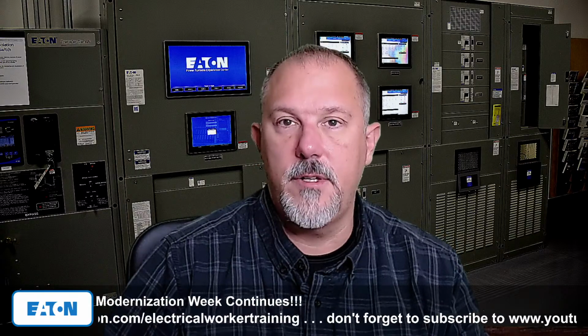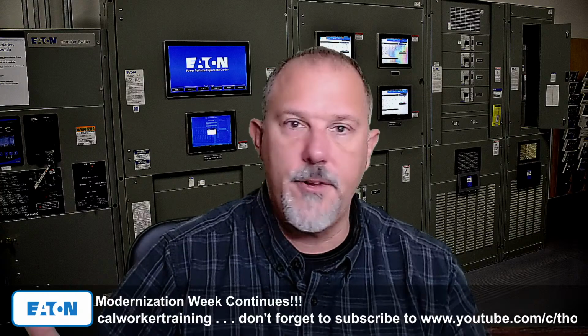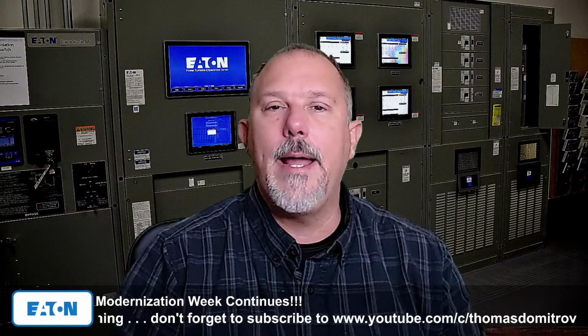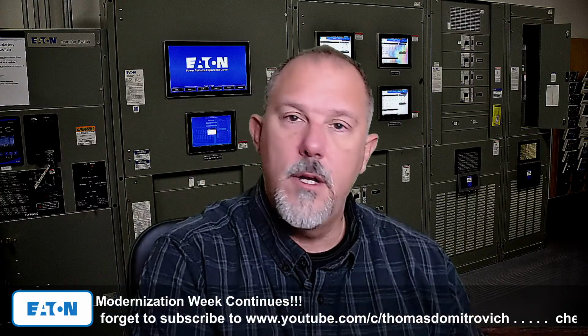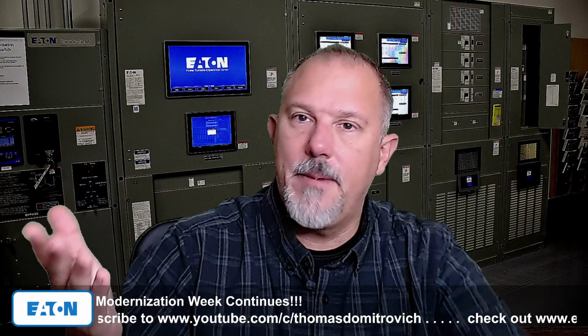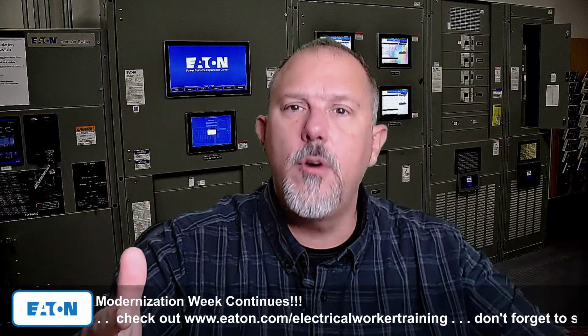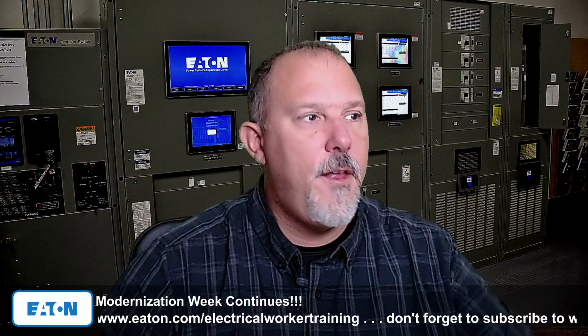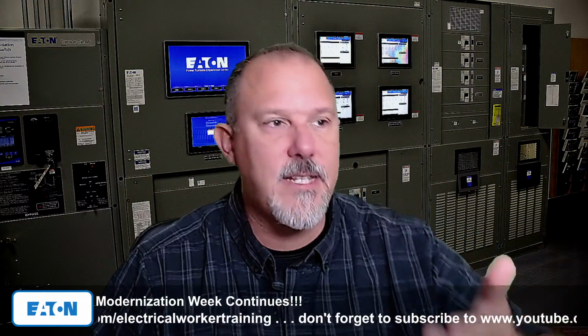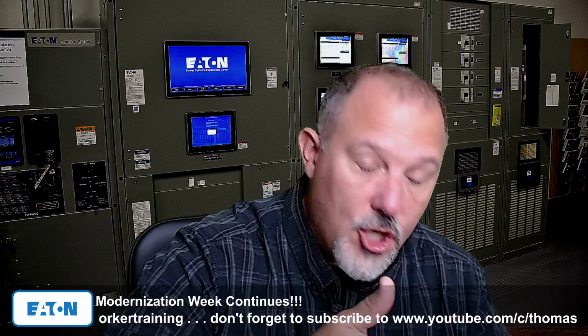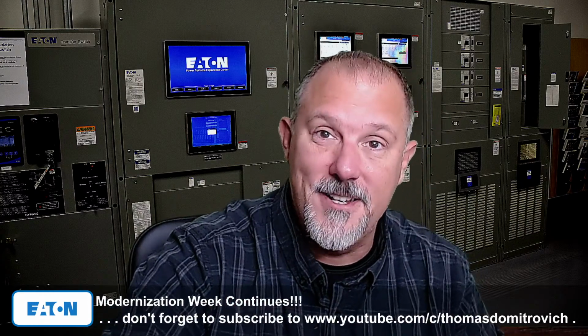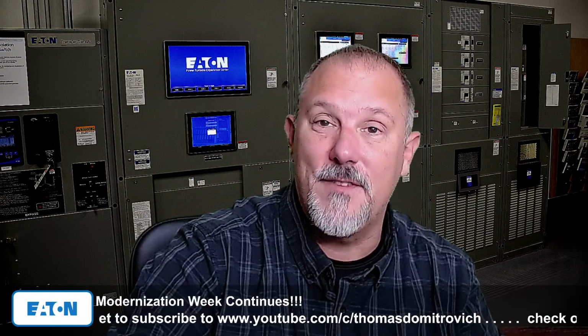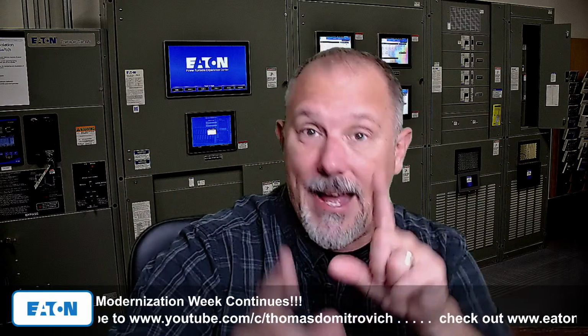They're prohibited now from being used. The code says you can't do that. And I don't know why we create a double standard for an HVAC unit. I mean, think about it. We have a light switch that the National Electrical Code and the entire industry are ready to rip their shirts off about. You're using the equipment grounding conductor to power these electronics on that light switch, that occupancy sensor. That's a violation of objectionable currents. And the code changed in multiple locations to prohibit the use of those types of light switch or those occupancy sensors.